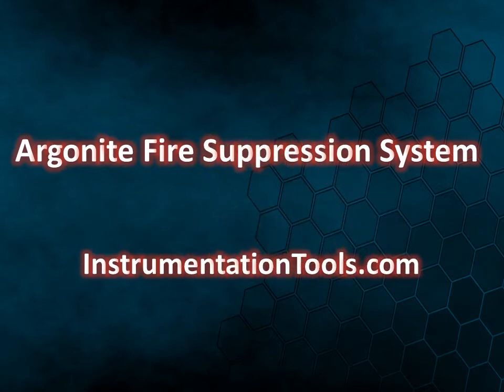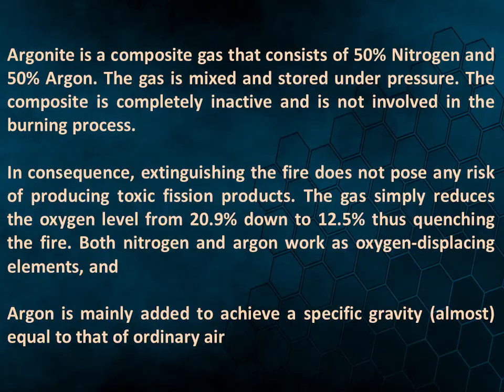Argonite Fire Suppression System by InstrumentationTools.com. Argonite is a composite gas that consists of 50% nitrogen and 50% argon. The gas is mixed and stored under pressure. The composite is completely inactive and is not involved in the burning process.